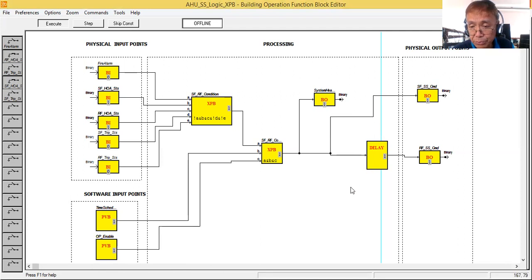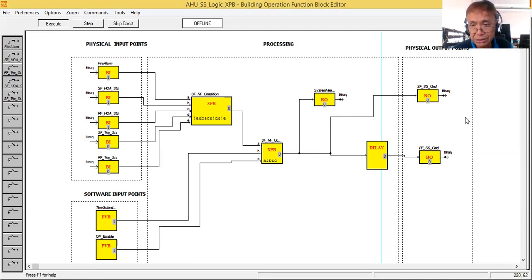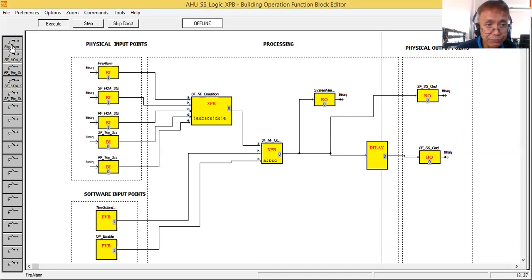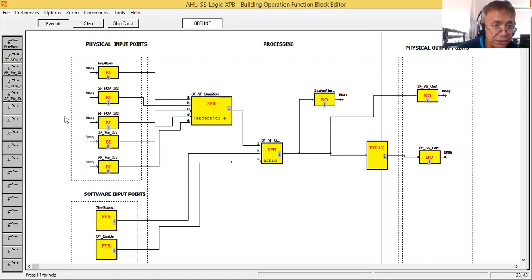Our control logic started the fans. Now let's simulate a fire alarm. As you can see, our control logic removes its command to the supply fan and return fan because there is a fire alarm. Now let me remove the fire alarm — immediately our control logic restarts the fans.